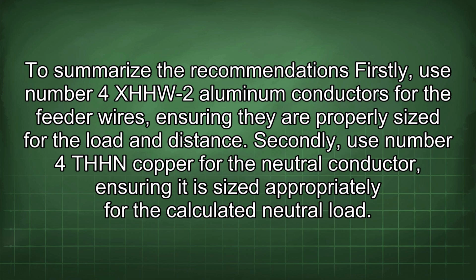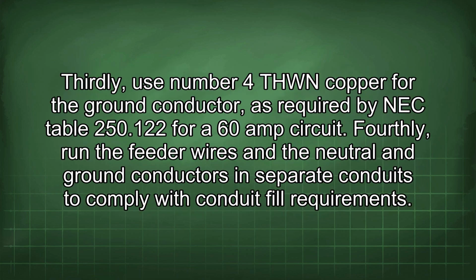Secondly, use number 4 THHN copper for the neutral conductor, ensuring it is sized appropriately for the calculated neutral load. Thirdly, use number 4 THWN copper for the ground conductor, as required by NEC Table 250.122 for a 60 amp circuit. Fourthly, run the feeder wires and the neutral and ground conductors in separate conduits to comply with conduit fill requirements.